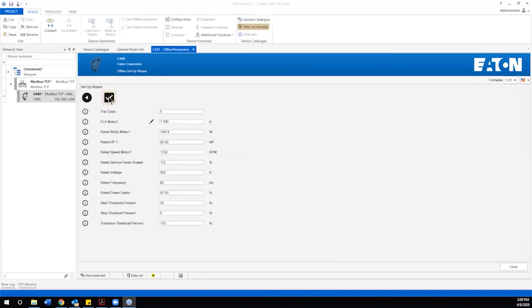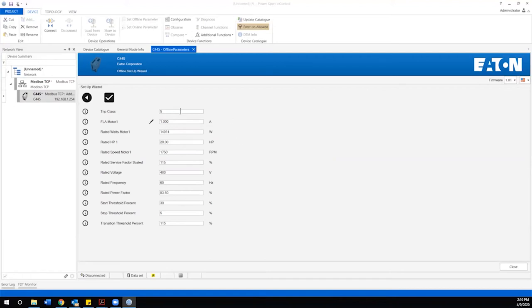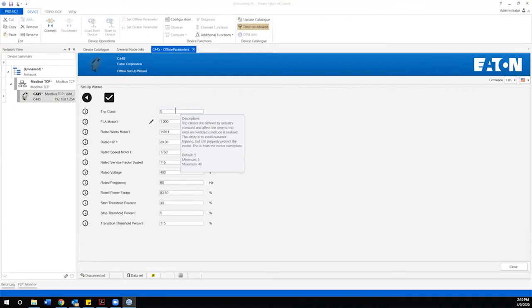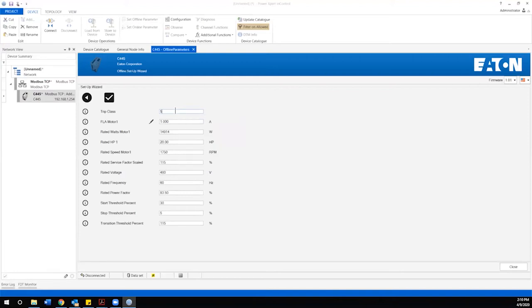Moving on to my next screen I need to fill in specific data associated with the motor. Most of this information is going to be found directly on the motor nameplate for the application that we're working with. First parameter we're going to want to set is the trip class and we have a default of 5. The range is 5 to 40. Common general motor application trip class is 20. In most applications you're going to be configuring, this would give a good well rounded overload curve and associated trip settings.